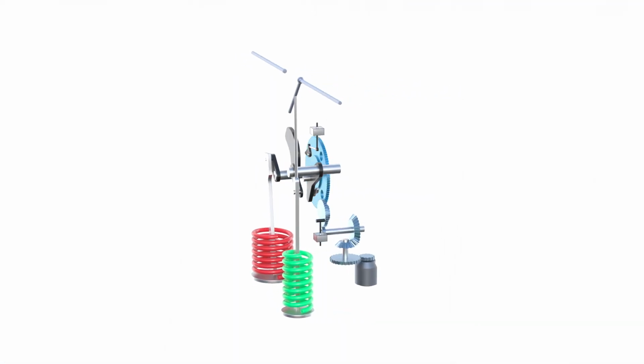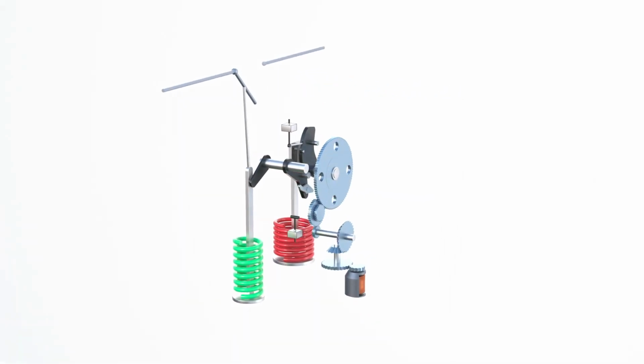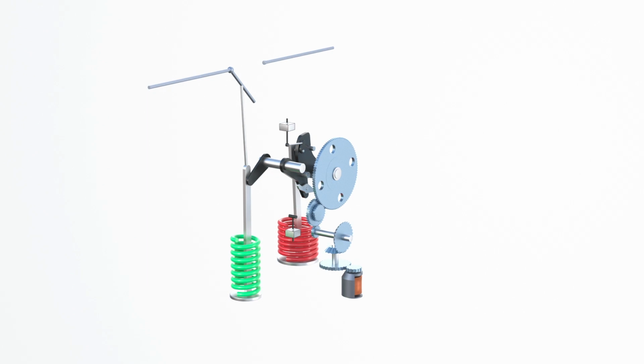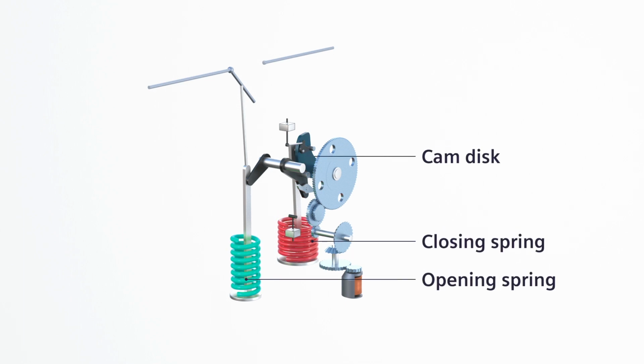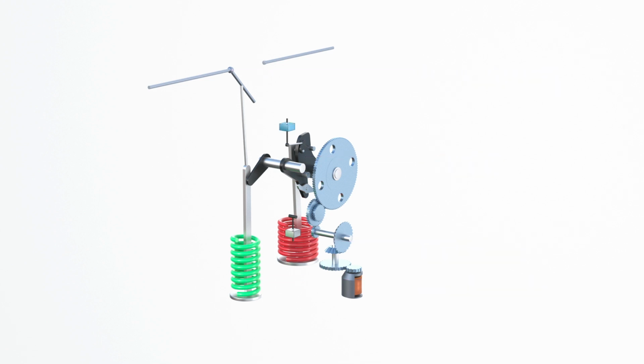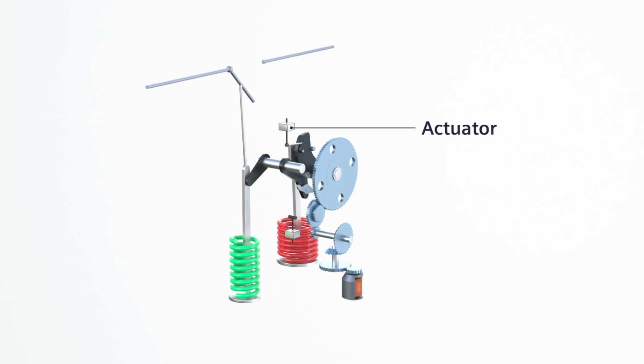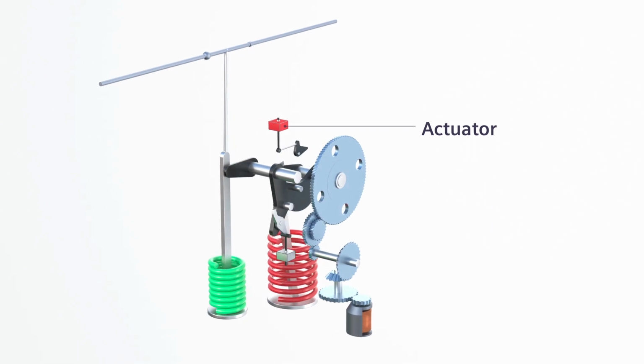The closing spring is charged by an electrical motor through a charging gear which disengages once the closing spring is fully charged. The switching cycles are triggered by electromechanical actuators and mechanical latches. As the closing operation takes place, the closing spring charges the opening spring through a cam disc. At the same time, the interrupter unit, which is coupled directly to the opening spring, will be closed.